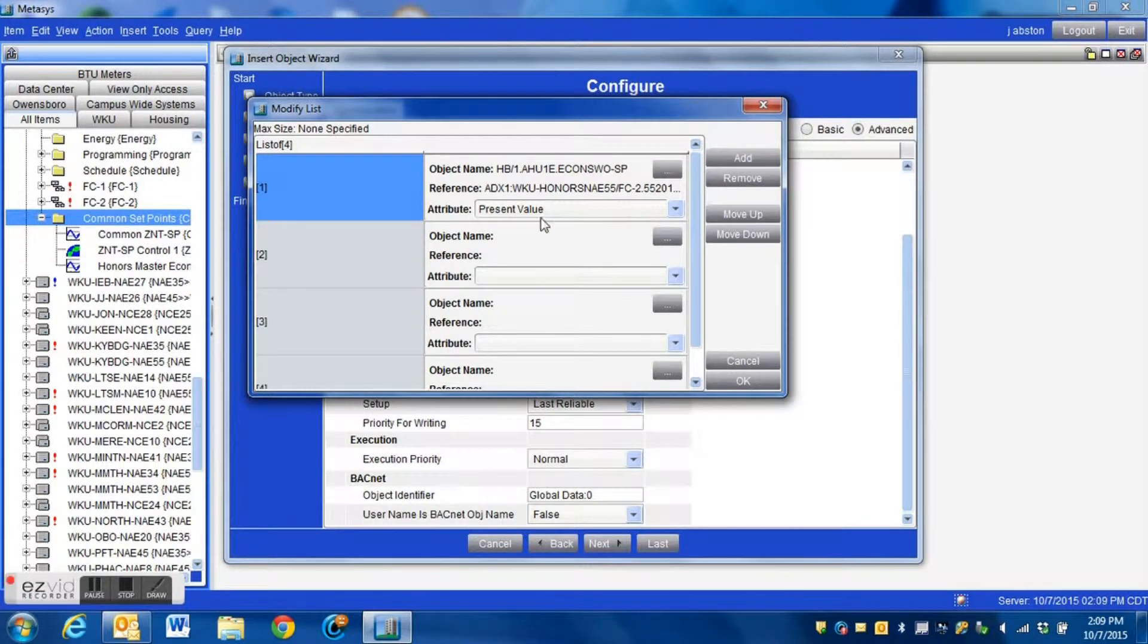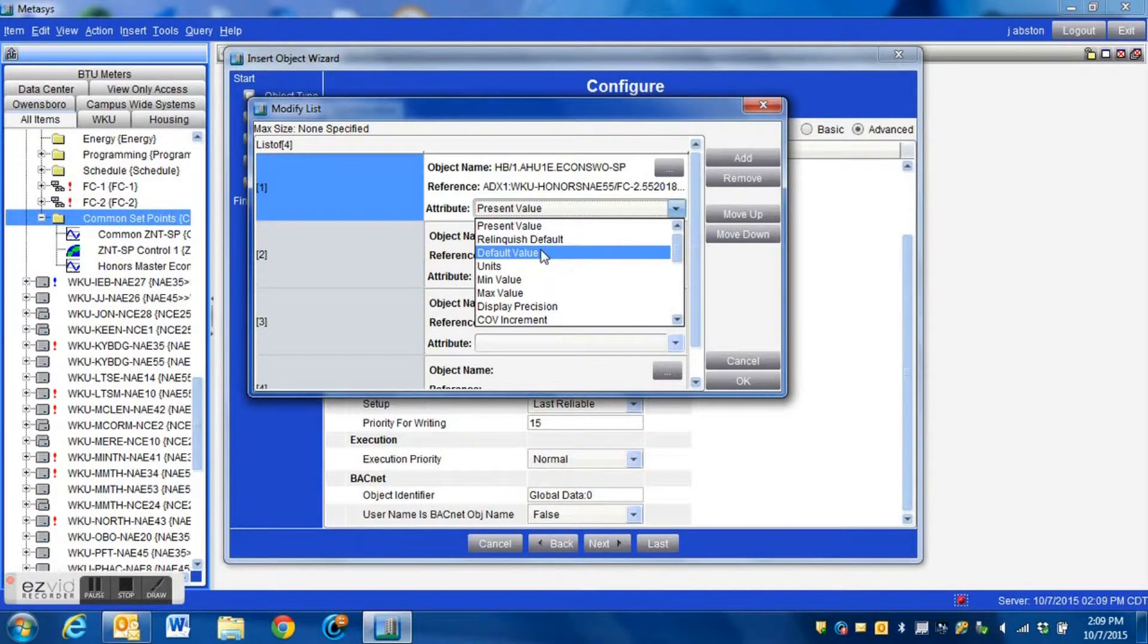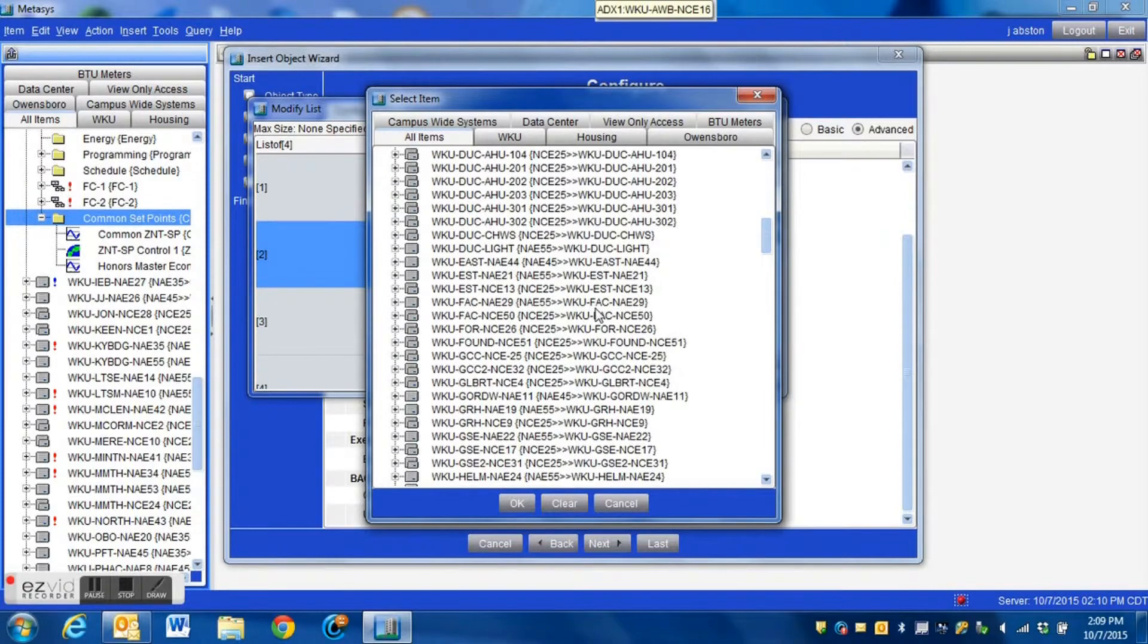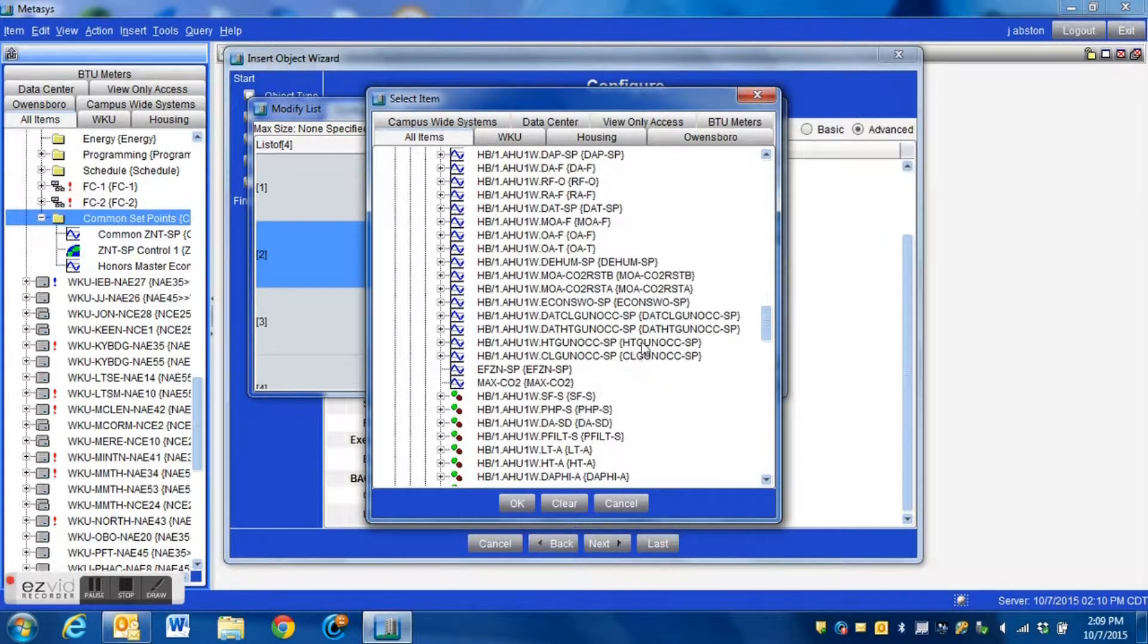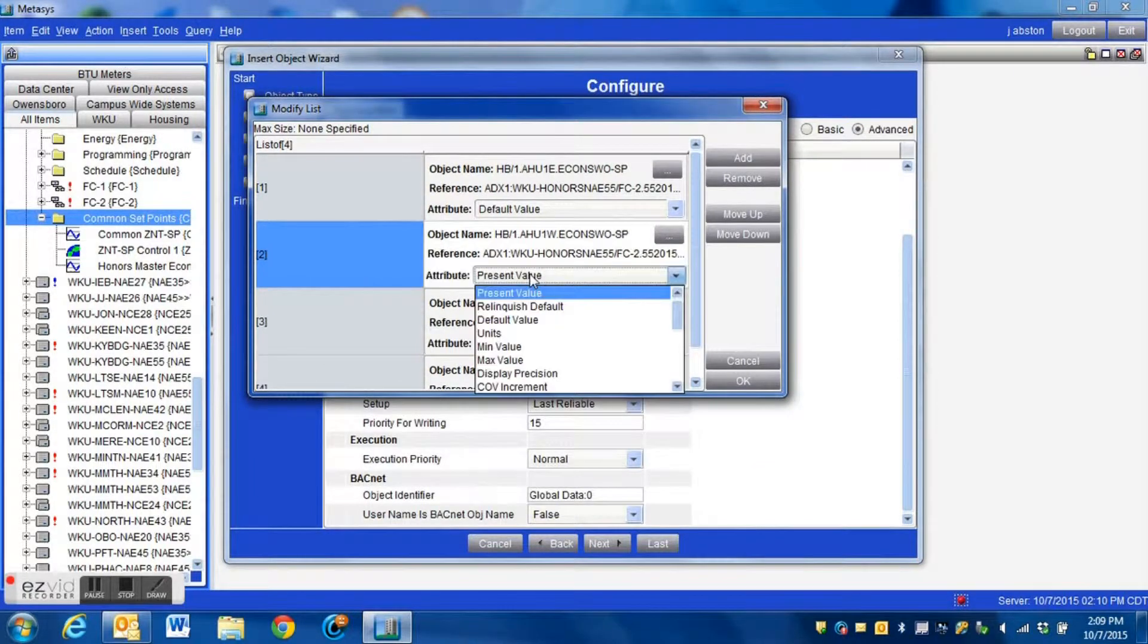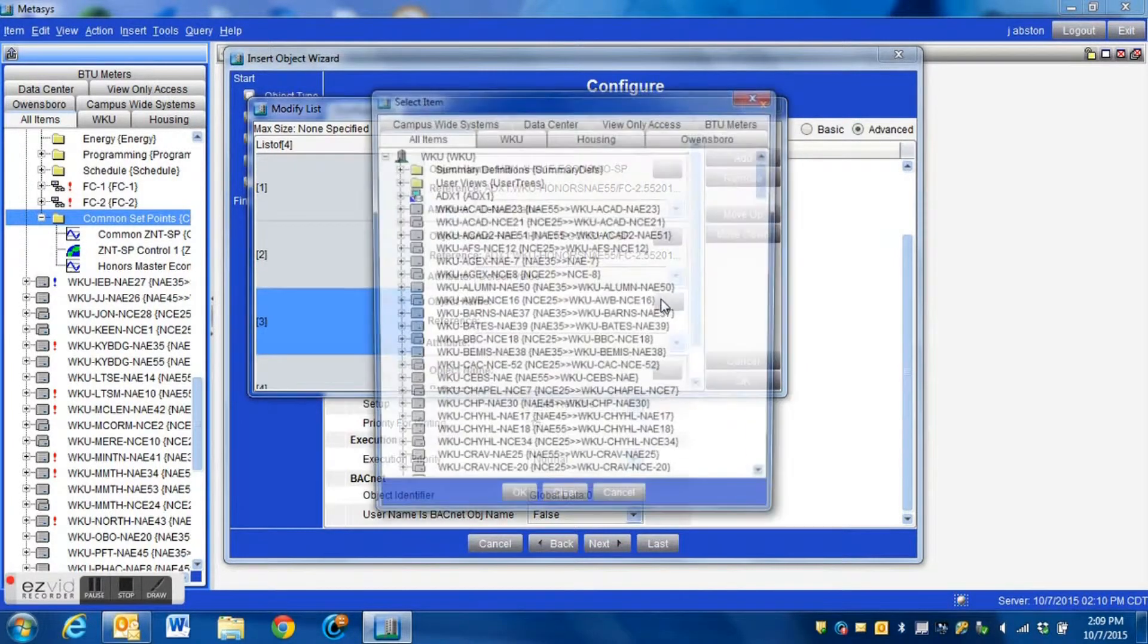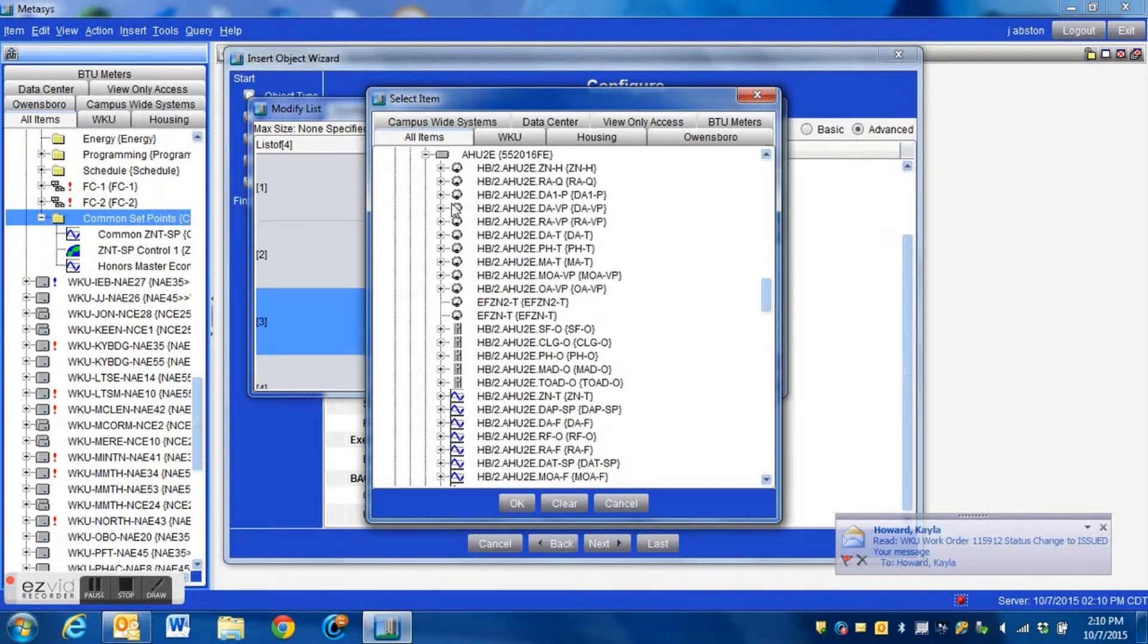Now then for these particular points we have got to change this from the present value to the default value. Different points are commanded differently within your system and these particular points when we go to command them it only gives us the option of changing the default value and we have to add that here. So we're going to go through each of these and add these points from each of the air handlers to our logic block. Just bear with me for a minute, it's pretty much the same in each of these, we just grab the economizer, change the block to the default value. There's a total of six air handlers in this building.